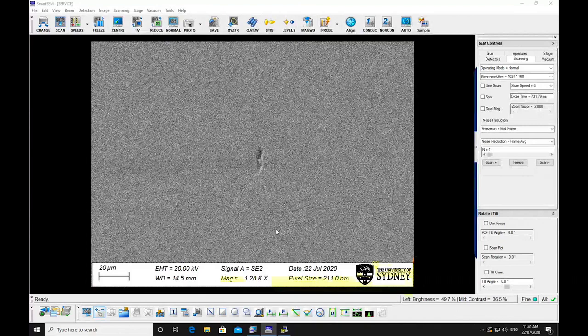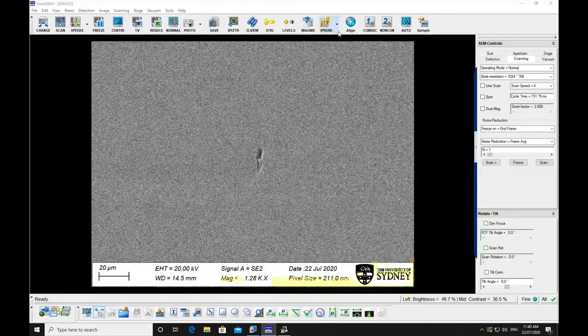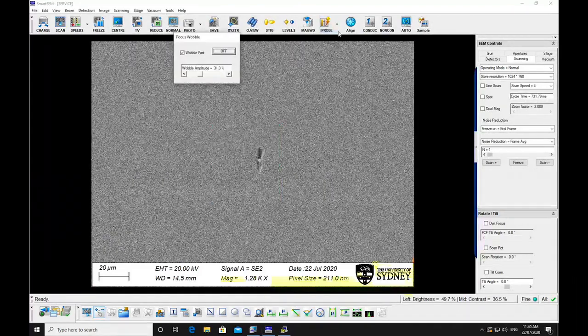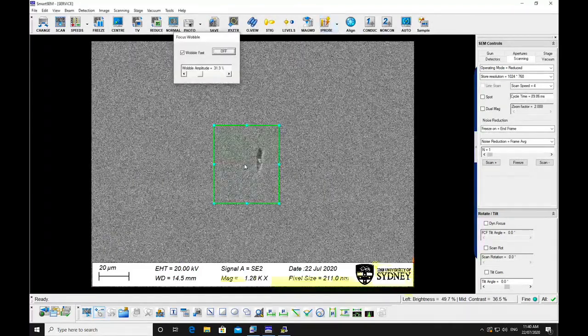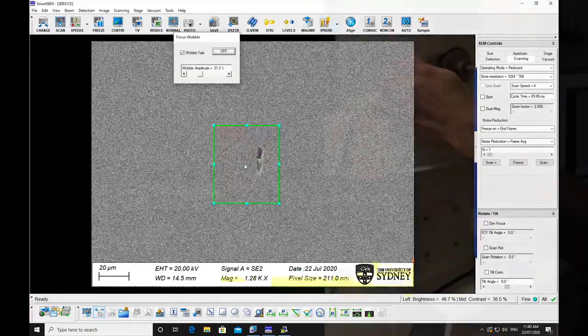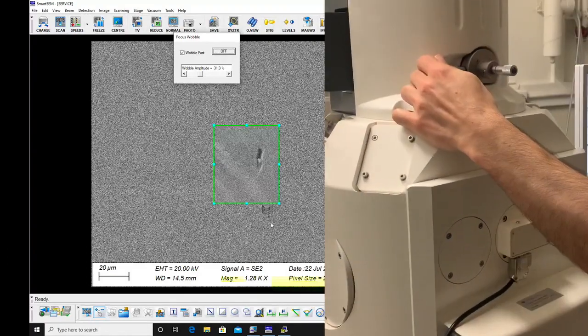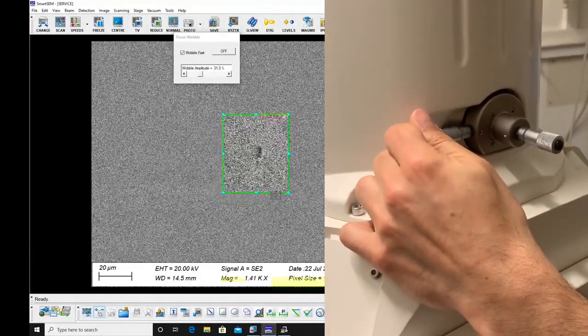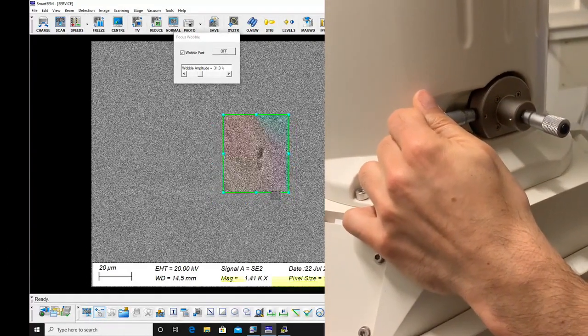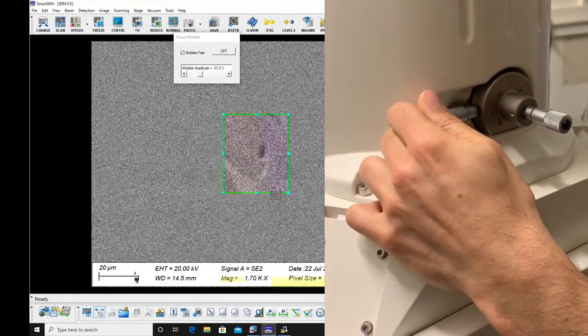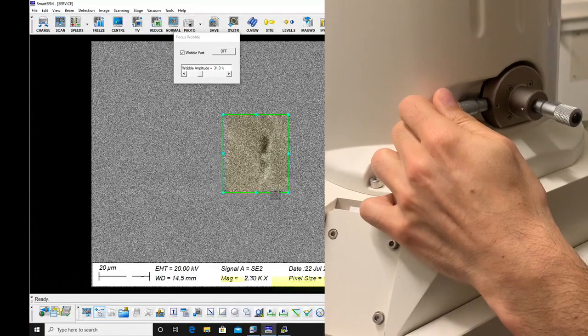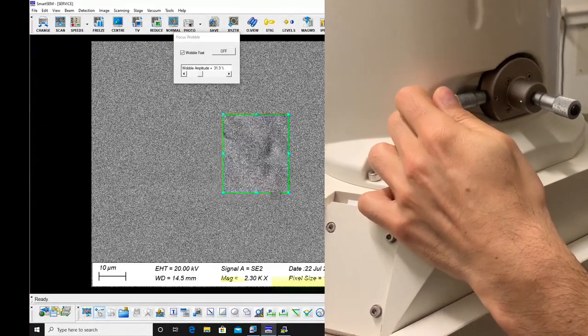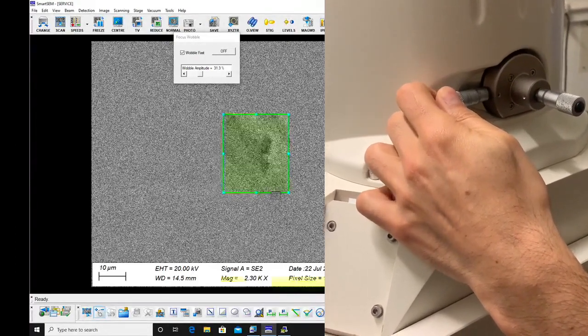Focus and stigmate the image at a high magnification and press the wobble button. Center the aperture manually by using the X and Y micrometers located on the microscope column. Minimize the movement as the focus wobbles.